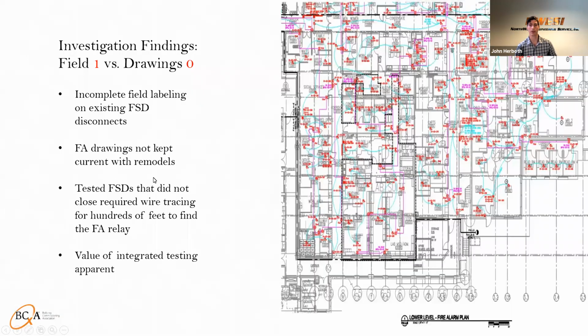And then there's also the problem when you have addressable components that they get added on to a relay because of the nearest addressable component. And if they don't do that right, sometimes on the wiring side, you can start impacting it as well, even if it can be picked out individually in the program.